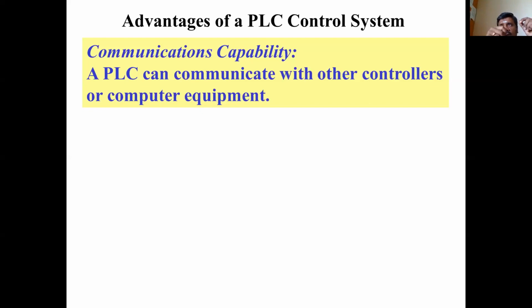And when you are connecting your system to the Ethernet for the internet, you might not be aware whether it has been inserted or not. Anyway, your internet will work. But the locking mechanism of the industrial Ethernet will be of high standard. You have a vibrant sound when you connect the industrial Ethernet to the Ethernet port, that it is connected, even after aging. And moreover, it can withstand high temperature, because sometimes it may be necessary to place the PLC in a high temperature. But if you are using a normal conventional RJ45 connector, it may not withstand the high temperature.